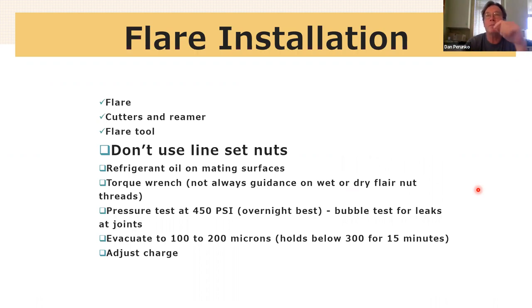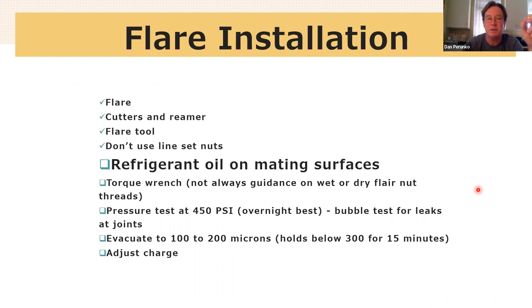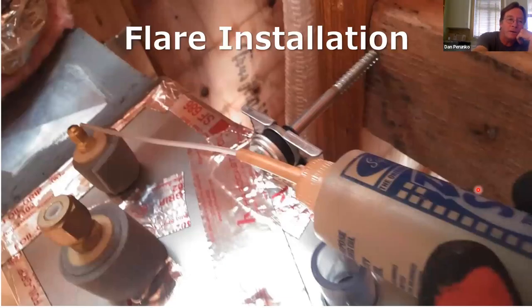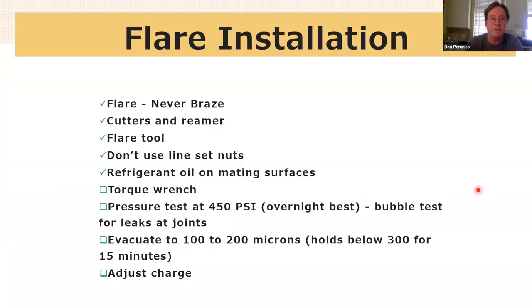The equipment manufacturers don't want us to use those. They're going to send stuff specific to their machines. They want us to use those. When you're making a flare, you put oil on the mating surface where the female and male portions of the flare connection come together so that the metals move effectively.